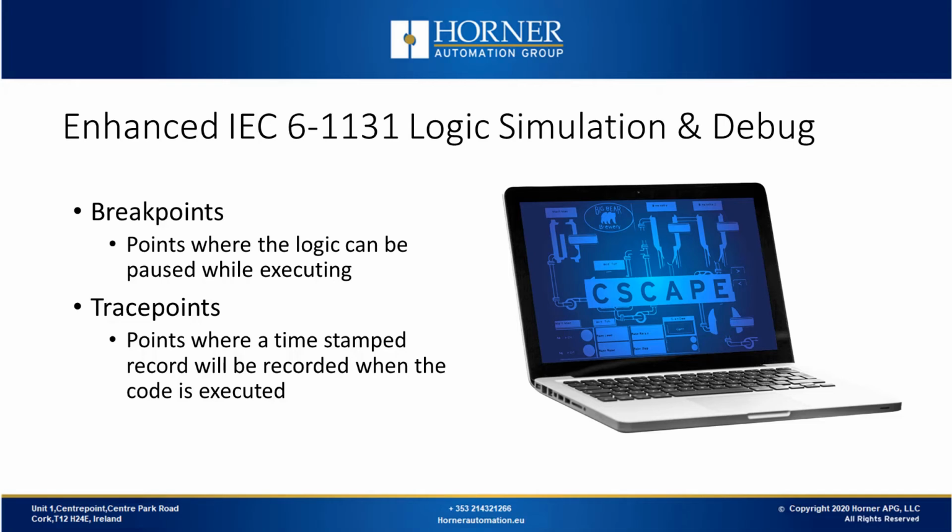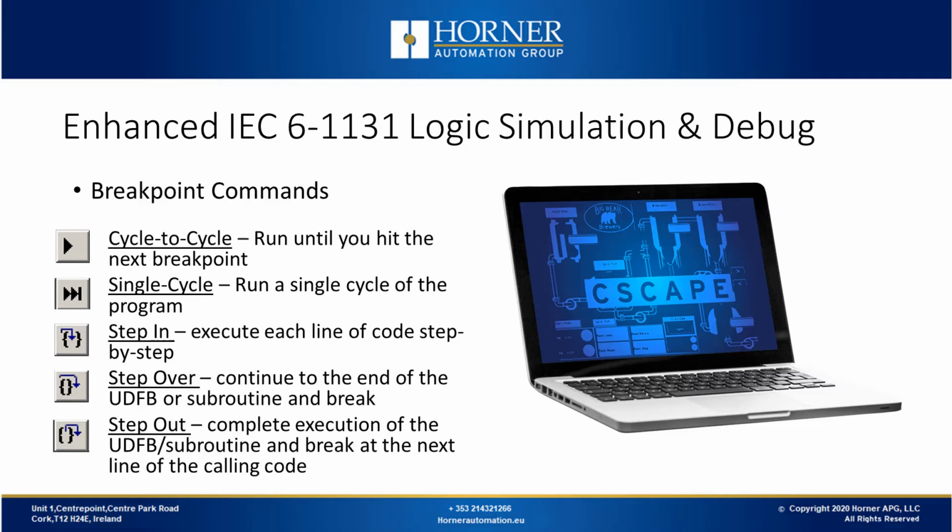Let's start with breakpoints. Breakpoints are flags that set points in the program where your logic can be paused while you're executing. You can place them anywhere you choose, and they're fully supported for structured text and ladder. We also have a feature called Tracepoints, which are set points that cause a timestamp to be created every time that logic is executed. They provide solid evidence that the logic did execute. After you set these breakpoints and tracepoints, there's a series of commands you can use to customize how you work your way through your program.